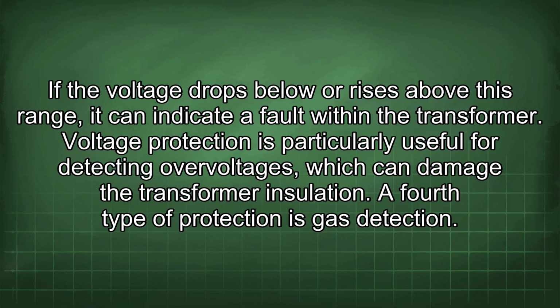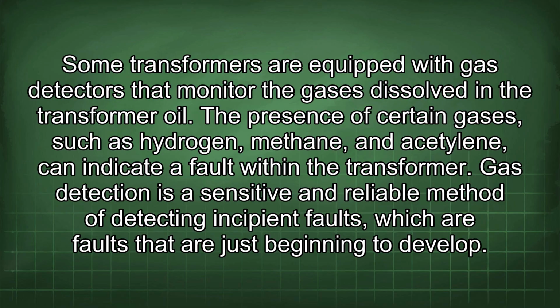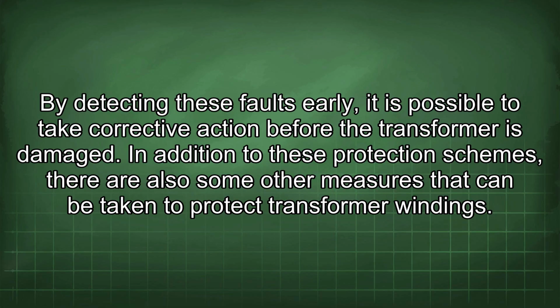A fourth type of protection is gas detection. Some transformers are equipped with gas detectors that monitor the gases dissolved in the transformer oil. The presence of certain gases, such as hydrogen, methane, and acetylene, can indicate a fault within the transformer. Gas detection is a sensitive and reliable method of detecting incipient faults, which are faults that are just beginning to develop. By detecting these faults early, it is possible to take corrective action before the transformer is damaged.